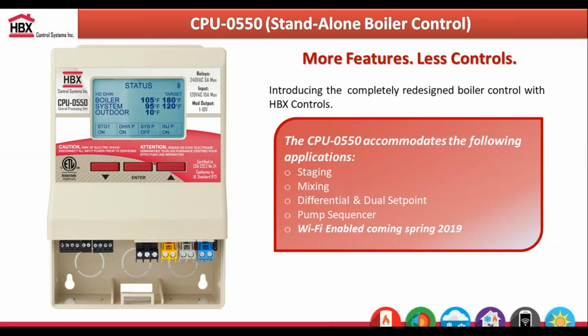In terms of our CPU 550, we really simplify this compared to the 1000 controller. With the 550, we can do 3 on and off boilers or a single modulating boiler for a 0 to 10. We can't do a 4 to 20 mA output. You'd have to use the CPU 1000 for that modulating type.